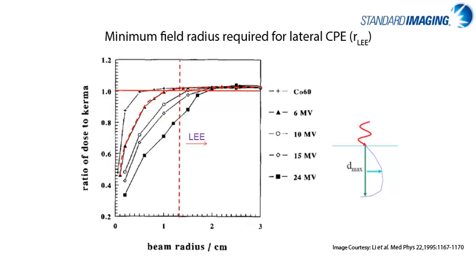which is our most commonly used energy, we need at a minimum a beam radius of approximately 15 mm to ensure CPE. Which when we also consider the electron range in the lateral direction as illustrated on the right, we must also acknowledge that this lateral range is nearly independent of energy and equal to the penumbra of the field as well. Thus, one could really feel safe with a field radius of 16 to 20 mm to ensure CPE with this energy.